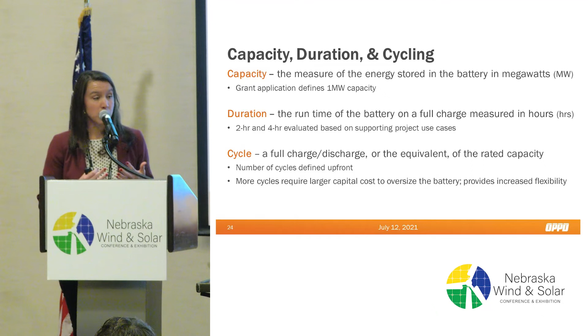As we were going through our learning, we understood that more cycles give us more flexibility. And again, as we're understanding how this would play in a reliability setting, but also in a market setting, this was something to consider. So where did we land? As you can see, we looked at 1 megawatt, 2-hour and 4-hour, and then 250 and 365 cycles a year. You can see the relative cost comparison here. Really, the biggest cost difference is in that duration. What we are trading off between A, B, or B and C is 2-hour versus 4-hour. Excuse me, the 2-hour is about 40% lower cost than 4-hour. So there's a significant trade-off in there.